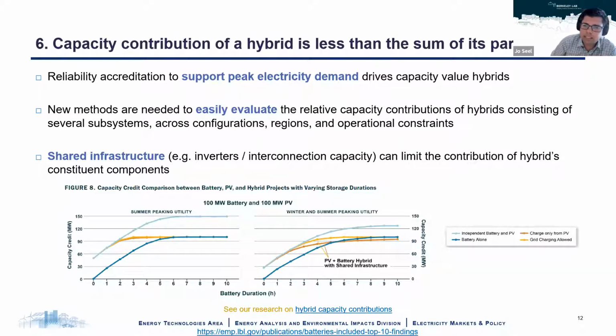The dark blue line here shows the capacity credit for a standalone battery, and it rises with its duration, reaching nearly 100% of capacity credit around 5 to 6 hours. A solar standalone project has a lower capacity credit. In our example, about 50% for a summer peaking utility and about 30% for a winter peaking utility.